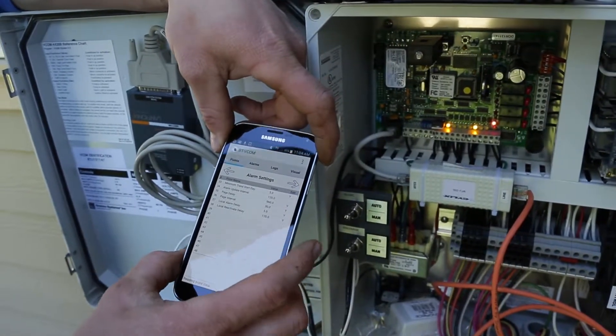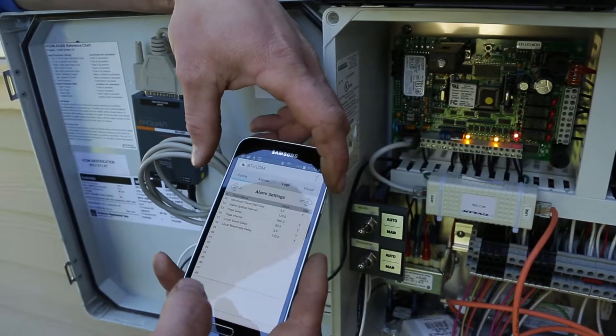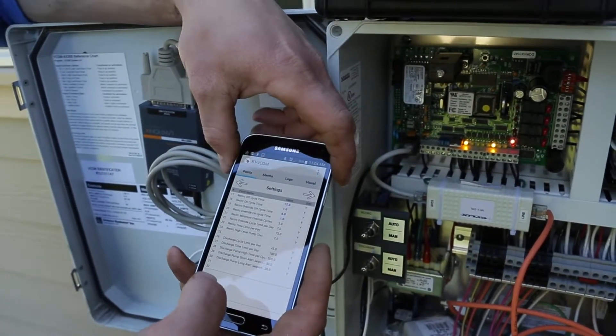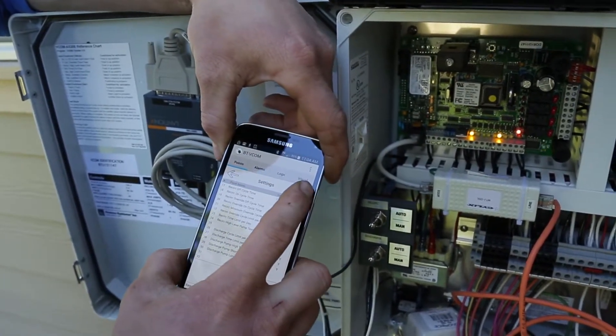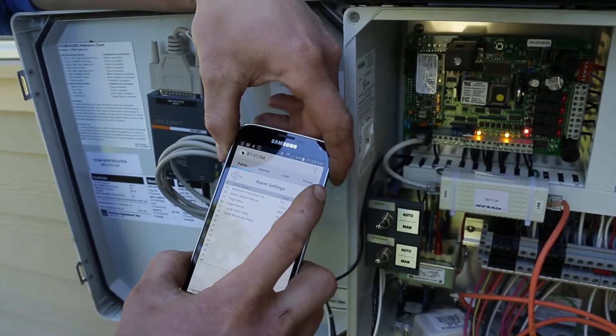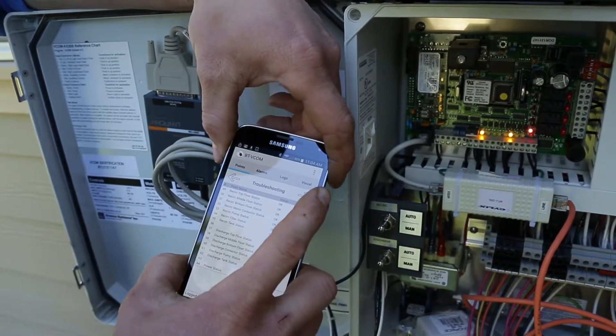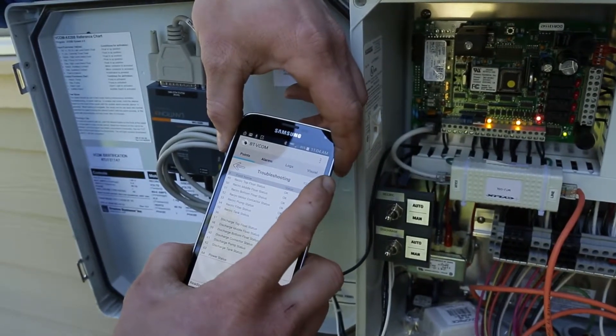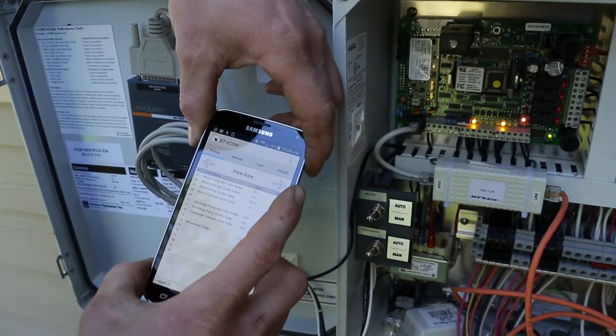Without the BTVCOM app and Bluetooth dongle, you either have to go into the Vericom website, upload the settings, and let it push them to the panel — since this is a network panel you don't dial directly into it — or you have to connect with a laptop that has a com port, which is kind of a pain. So this is really the best way to interface with these panels and make changes.